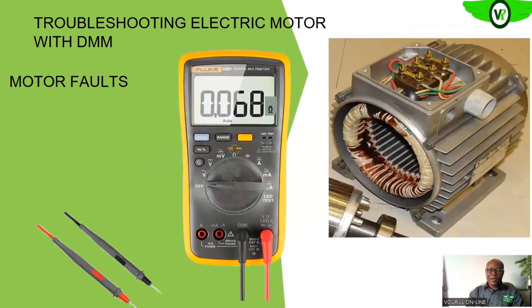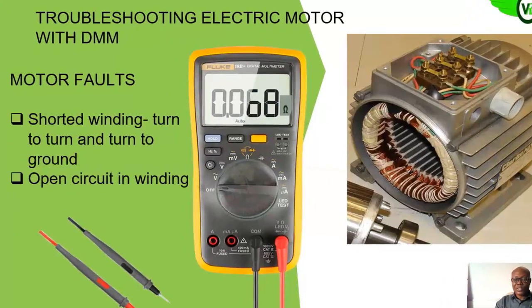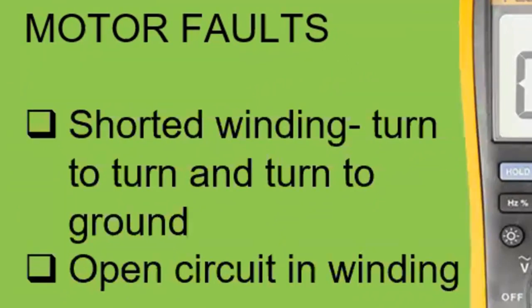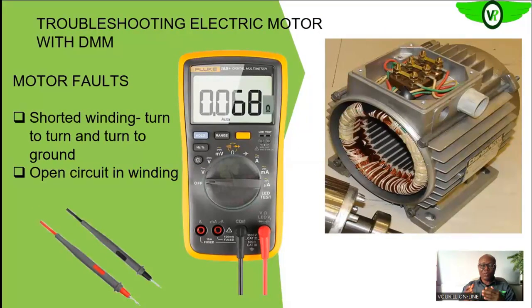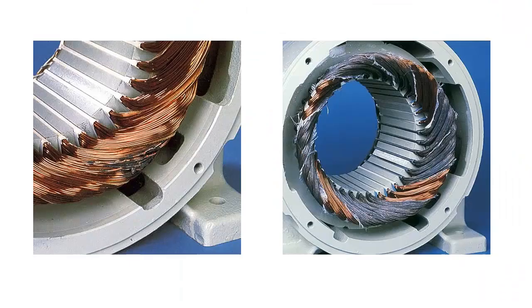Then another problem that is common too is the open circuit in the winding. Remember, the current flowing through the winding is expected to go all through the course of the winding and then out to the finish terminal, from start to finish. But if there is an open circuit, it means the winding is not complete. So there won't be flow of electricity, that magnetic field will not be created, and the motor will not work. In the case of a three-phase motor, if one phase is open, then we may have a case of single phasing of the electric motor. That is a real problem to the electric motor circuit. Okay, that is the second problem that is common with the electric motor.